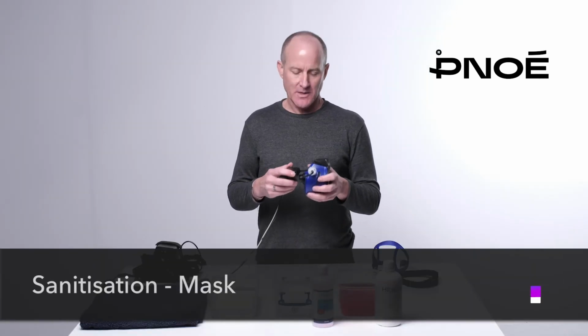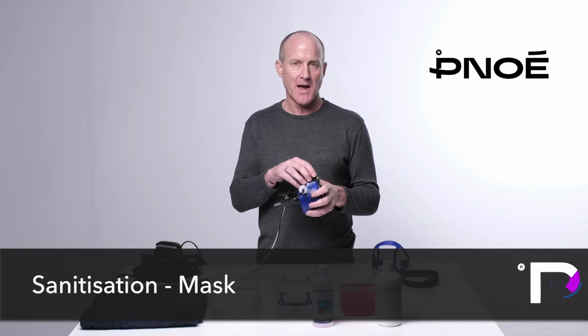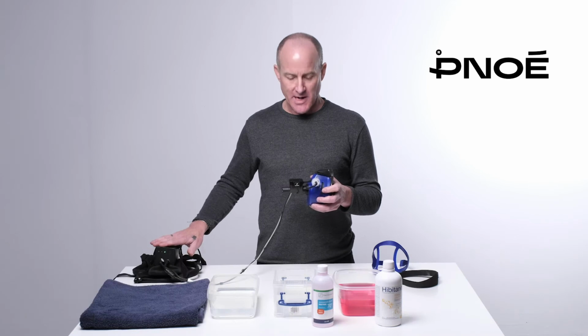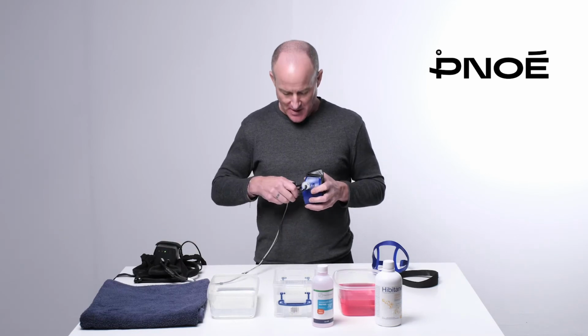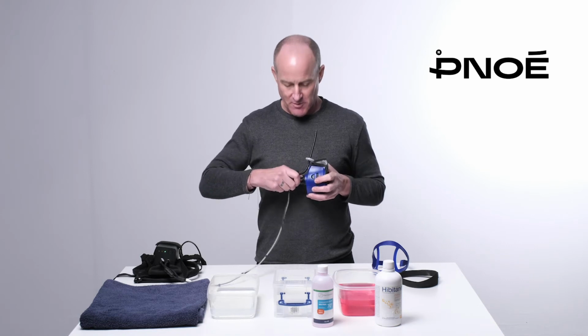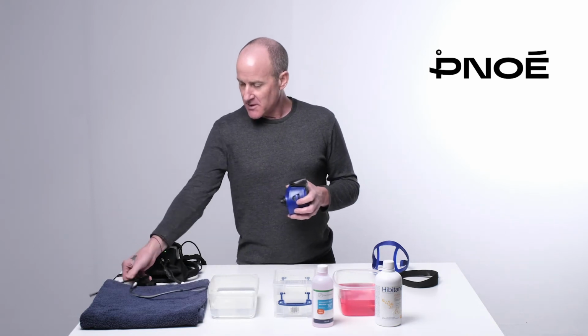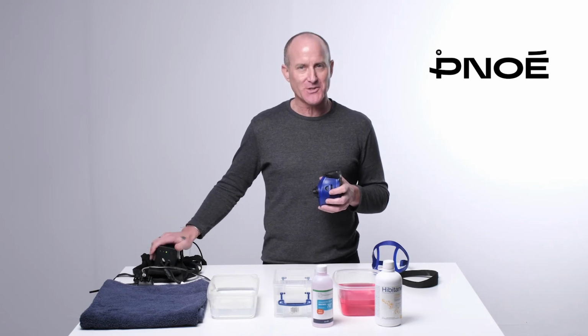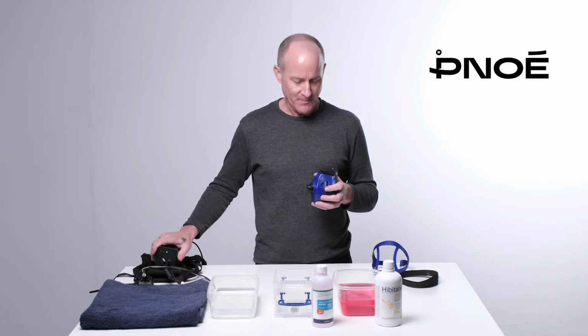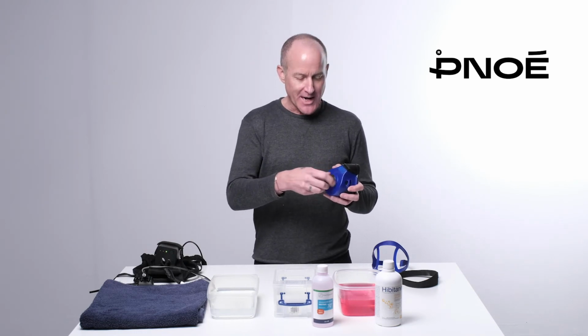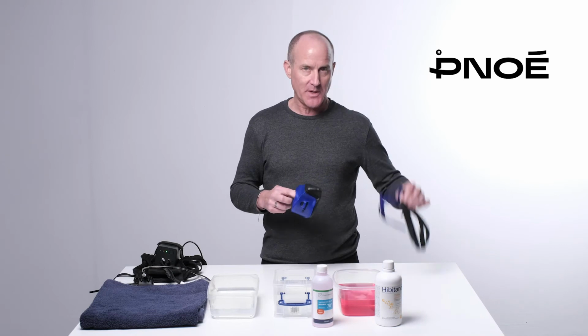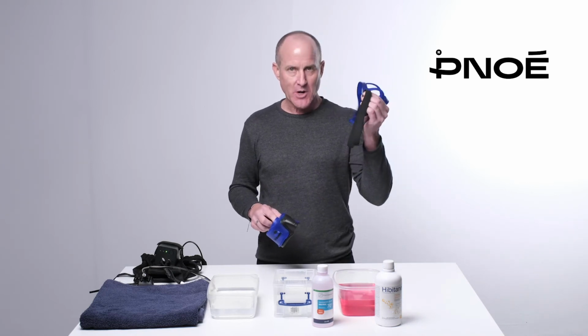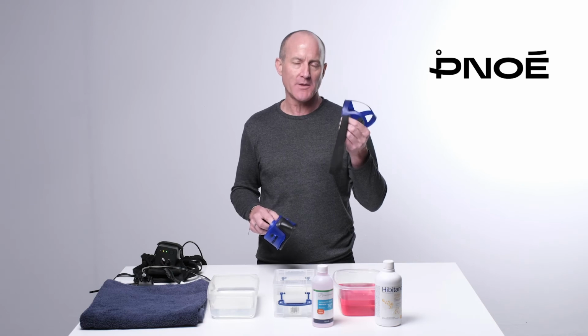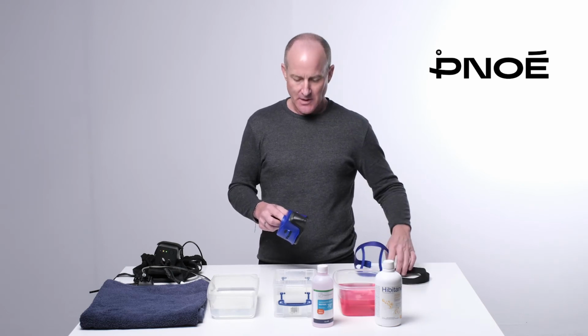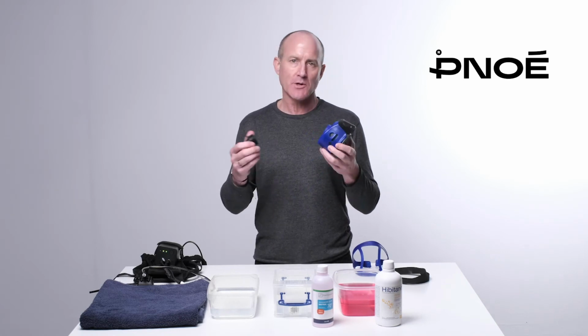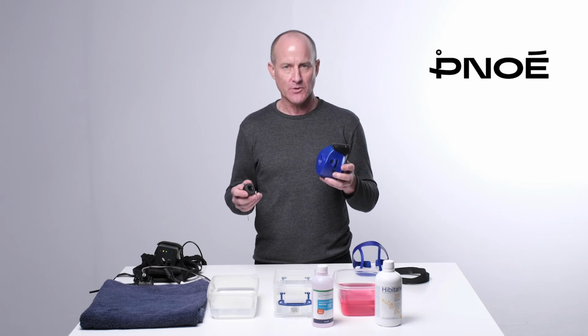It's imperative between customers that you fully sanitize and clean the masks. To do so, make sure you disconnect the mask from the flow sensor. You can do that by removing the rubber tube and removing the flow sensor. It's a great opportunity to charge your device and your power bank at this time. You're going to unscrew your adapter from the mask and take off the headpiece and the strap. The headpiece and strap can be washed in warm soapy water, then rinsed in clean water and hung to dry. You're going to take the mask and the adapter, or adapters if you're using the antibacterial and antiviral filter.